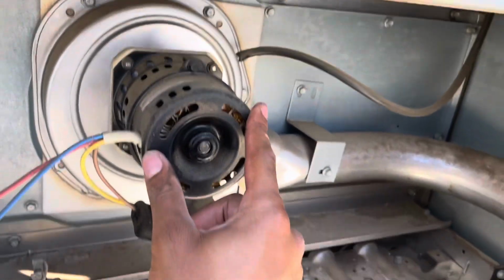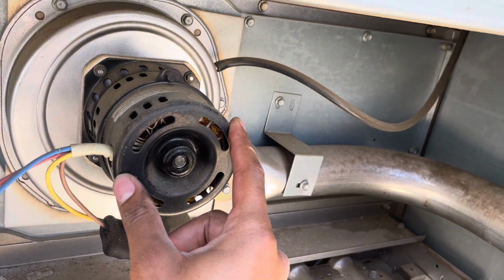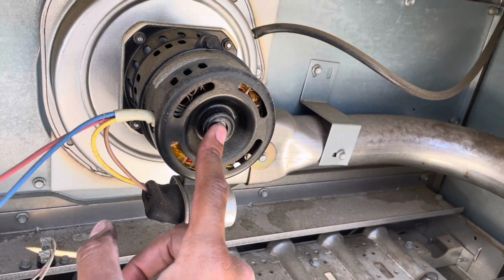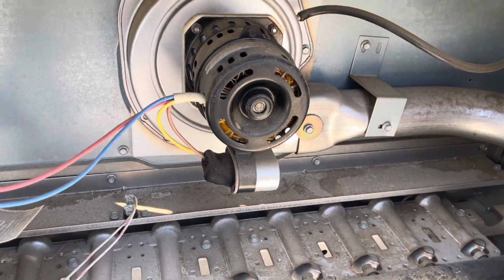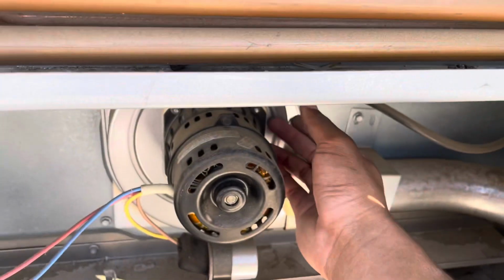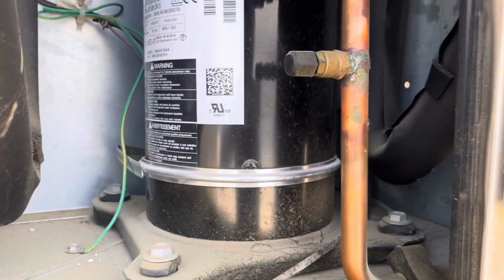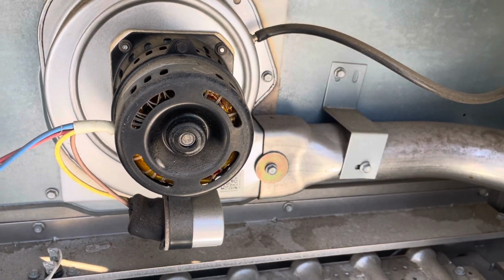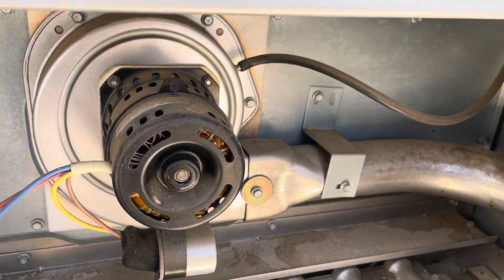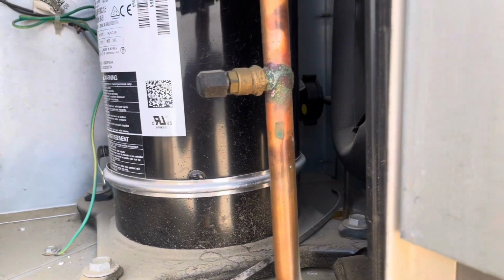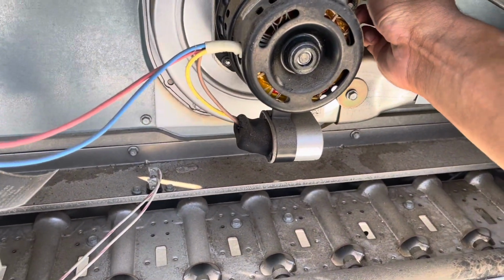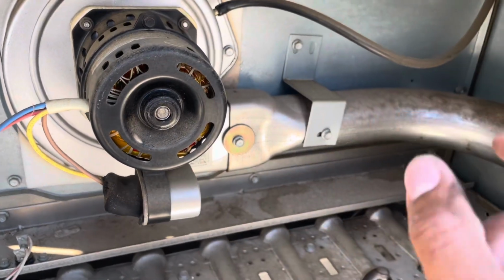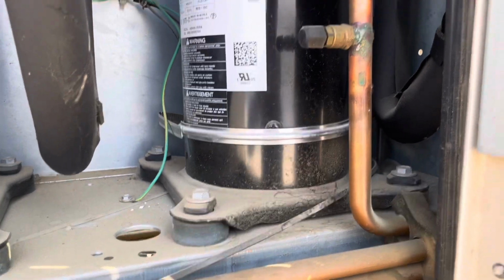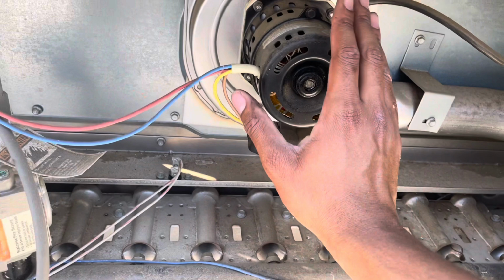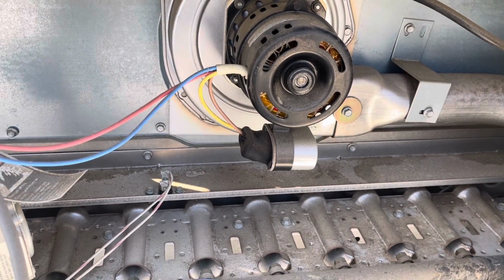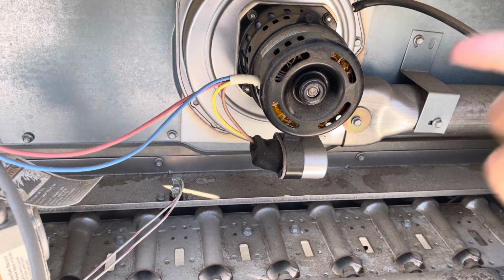So the inducer motor basically pulls a vacuum through the heat exchanger and also through the pressure switch. The pressure switch is there to prove that the inducer motor is running like it should. So you actually have a vacuum being pulled through this hose, all the way to that pressure switch, and that pressure switch is rated for a particular value of inches of water column. I don't know what these are rated for, but you can look on the actual switch itself and see the rating. Once that value is achieved, the pressure switch will close. They're normally open, but once the vacuum is pulled, the pressure switch will close, again to prove that the inducer motor is working like it should. The control board sees that and continues with the cycle. And the next thing that happens is the igniter.